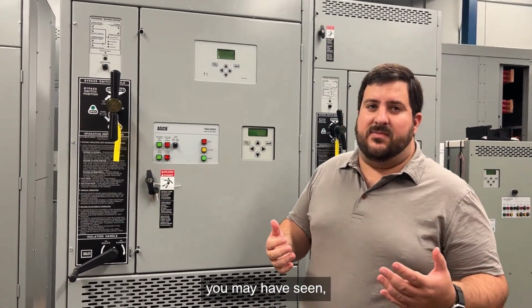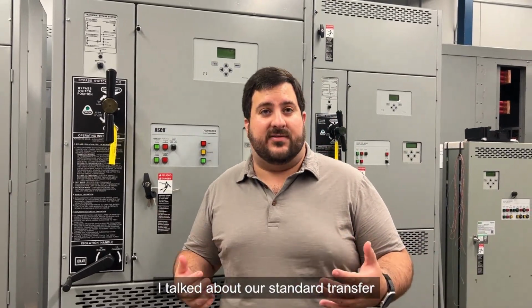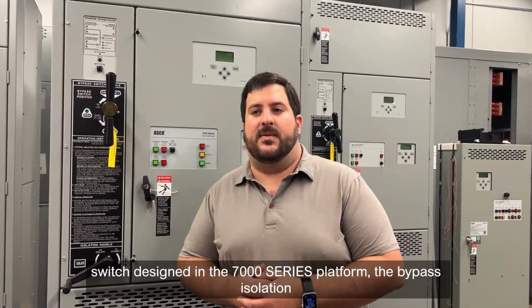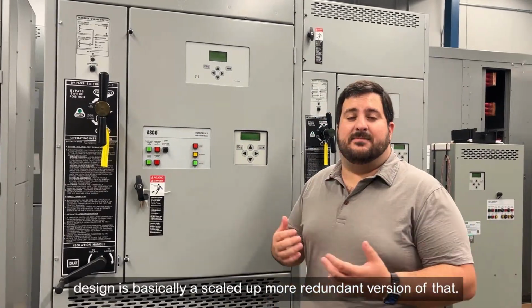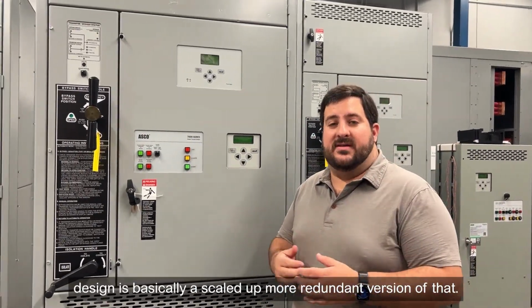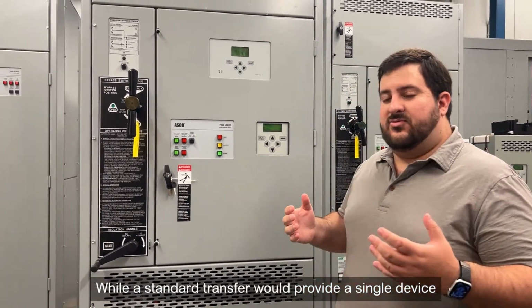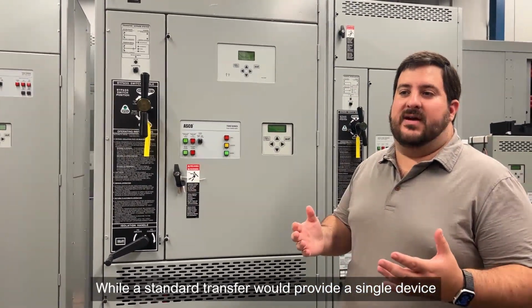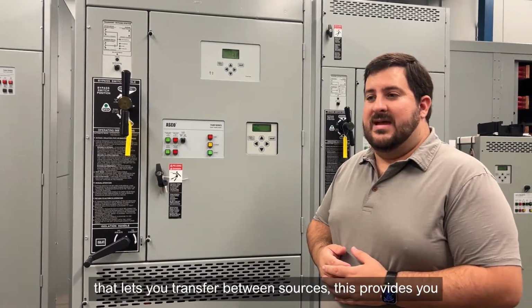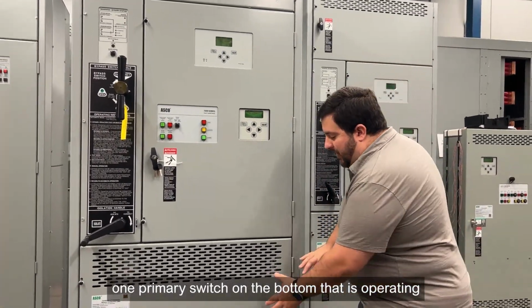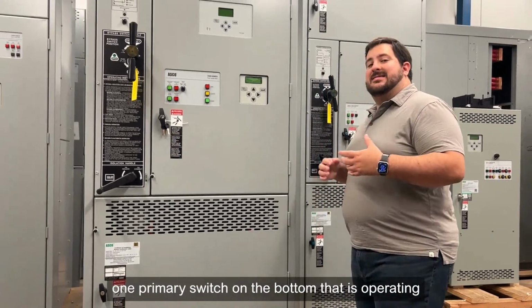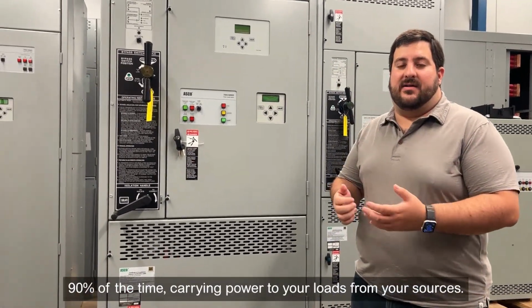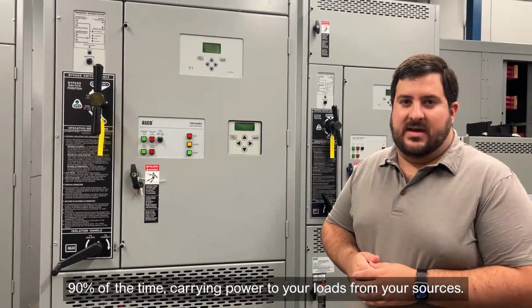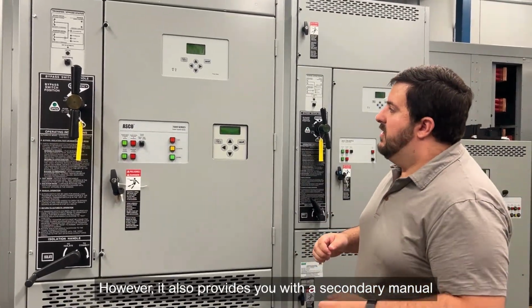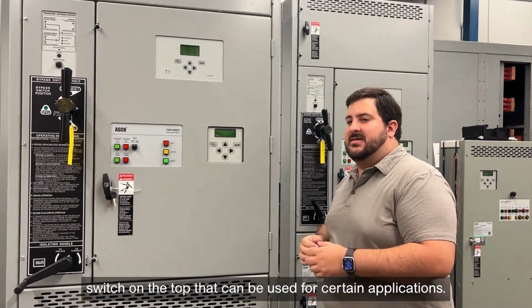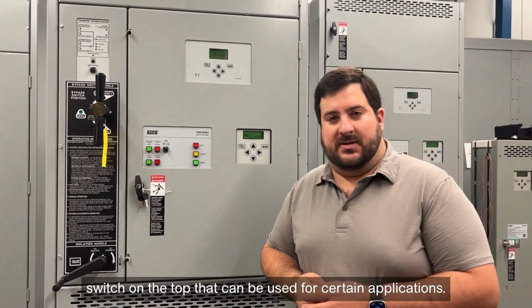In a previous video you may have seen, I talked about our standard transfer switch designs in the 7000 series platform. The bypass isolation design is basically a scaled up, more redundant version of that. While a standard transfer switch provides a single device that lets you transfer between sources, this provides you one primary switch on the bottom that is operating 90% of the time, carrying power to your loads from your sources. However, it also provides you with a secondary manual switch on the top that can be used for certain applications.